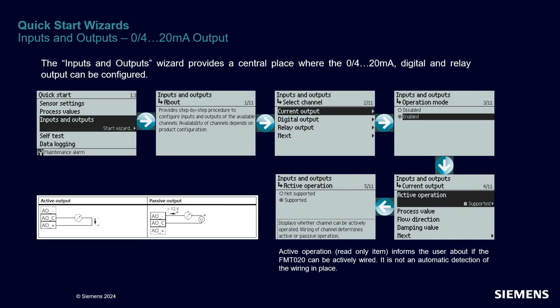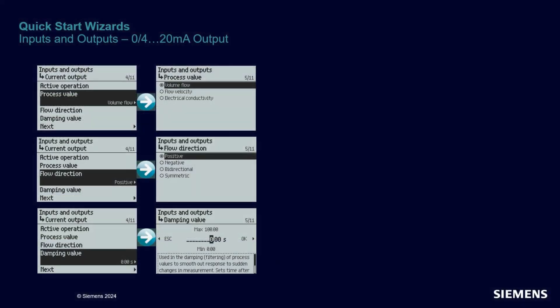For the classic current loop output, you start by choosing whether active operation mode is supported — this depends on your wiring. Then you select the process value of interest amongst three possibilities: volume flow, flow velocity, and the new electrical conductivity.